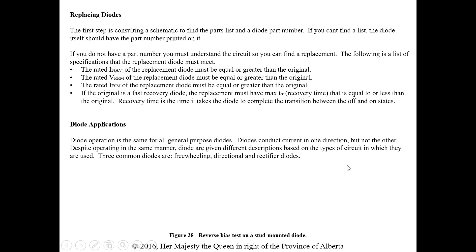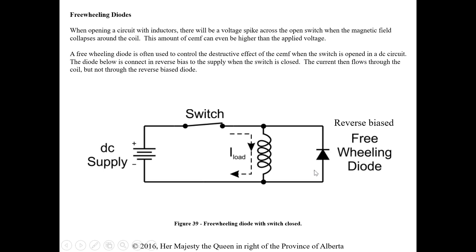Despite operating in the same manner, diodes are given different descriptions based on the types of circuits they're used in. Three common types are freewheeling, directional, and rectifier. Freewheeling diodes — when opening a circuit with inductors, there will be a voltage spike across the open switch when the magnetic field collapses around the coil. This CEMF can be even higher than the applied voltage. In a DC circuit, the coil builds a magnetic field that stays magnetized until the switch opens, then the field collapses and sends voltage back into the circuit, potentially arcing across the open switch and destroying components.